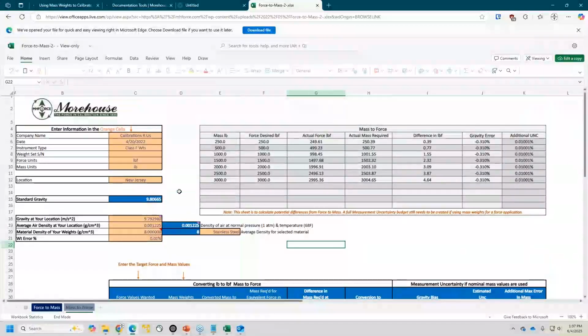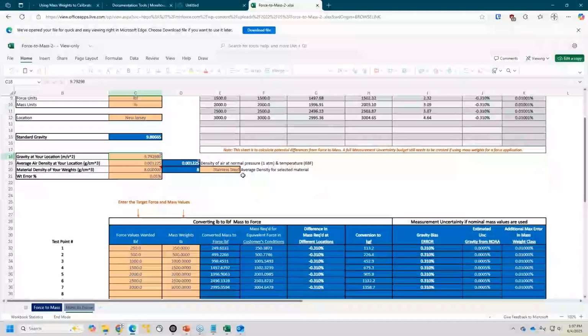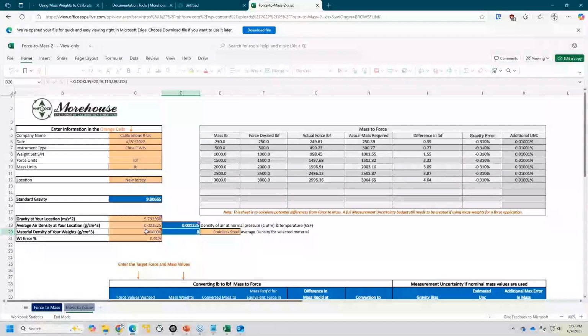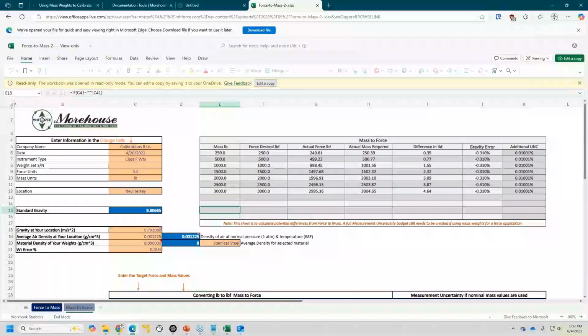And we wrote a guidance document for HOA. So if you're using class F weights, not a big deal. You can use them all day long. You put the gravity in at your location. You take a guesstimate on air density. Local airports and such can give you something very close at normal air pressure. Material density is not going to make the biggest deal. You can play around with that. You can use different material densities, say from the Machinist's Handbook, and some other things in there.